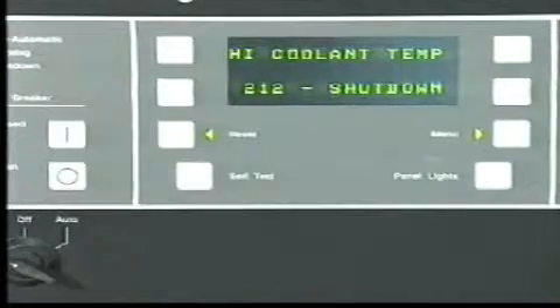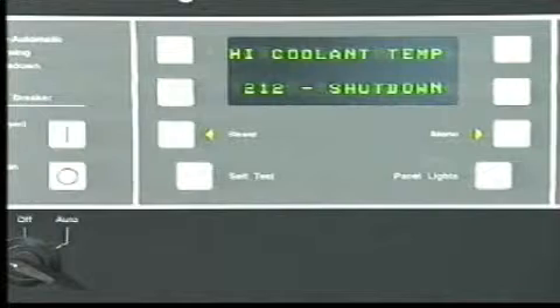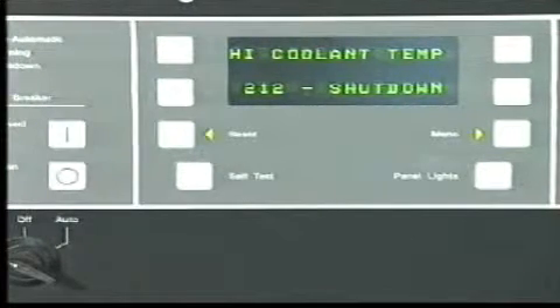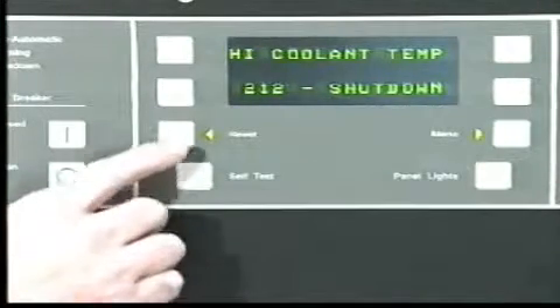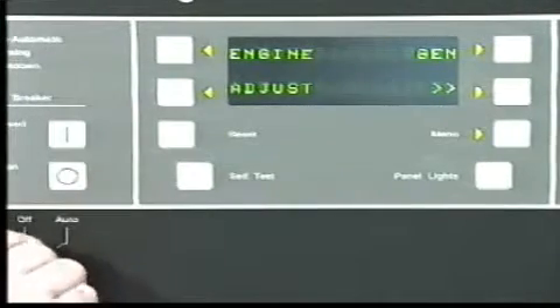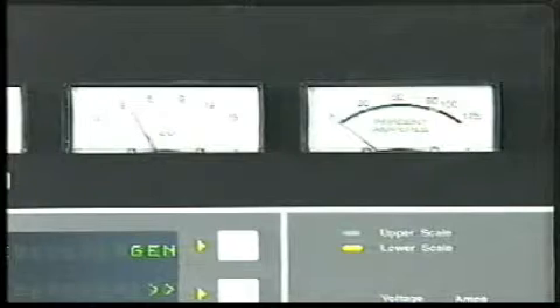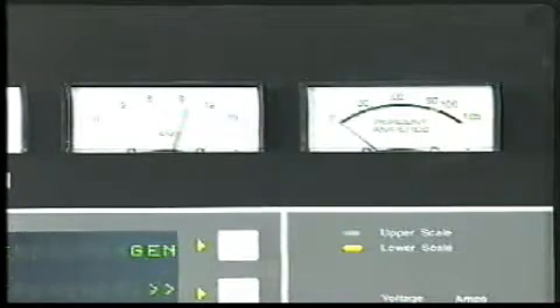It's as if the generating set actually sends out signals to you to explain the problems which create warning conditions, and if there's an actual fault shutdown, such as high coolant temperature, it tells you why, and digitally displays a reference on where to find the best route to clear the fault. Once the fault's cleared, just press the reset button, and the generator set can be started again.